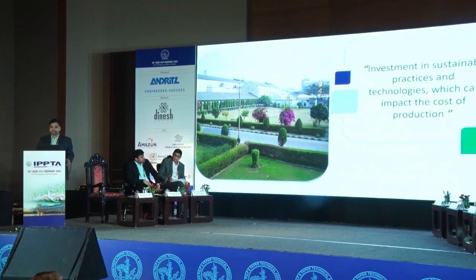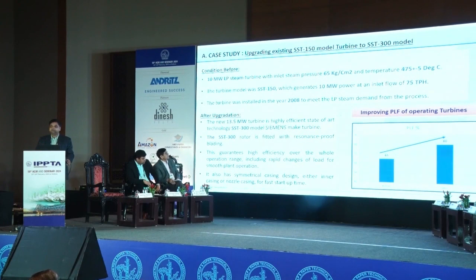Last, investing in sustainable practices and technologies. We have invested in upgrading our turbines, which were earlier of the SST 150 model and were not as efficient as per our requirement. After upgradation, we now have SST 300. The rotor is fitted with resonance proof blading, which guarantees high efficiency over the operating range, including rapid change of load in plant operation.